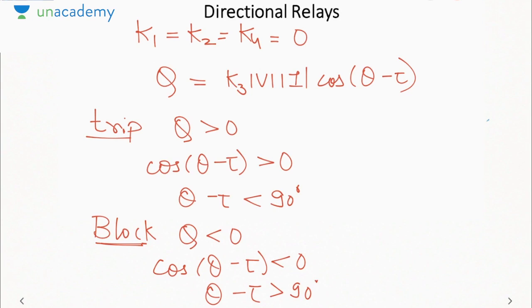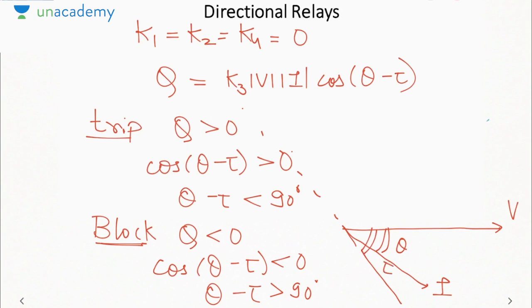So now how do we represent it in terms of a diagram or graphically? Now suppose this is my voltage phasor. Then for lagging current, the relay must operate. So suppose this is the current I. It is lagging by an angle theta. Now since tau is an adjustable parameter, let me call that this is the angle tau. Now if you see, when theta is equal to tau, cos(theta minus tau) will be 1. So torque will be maximum. Hence this will be called the maximum Q line. The torque will be maximum whenever theta is equal to tau.